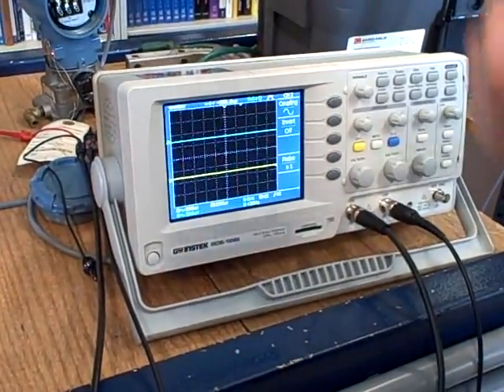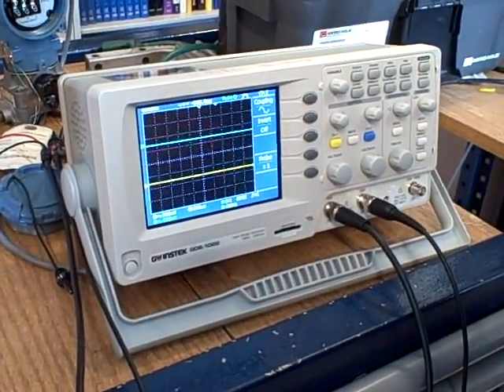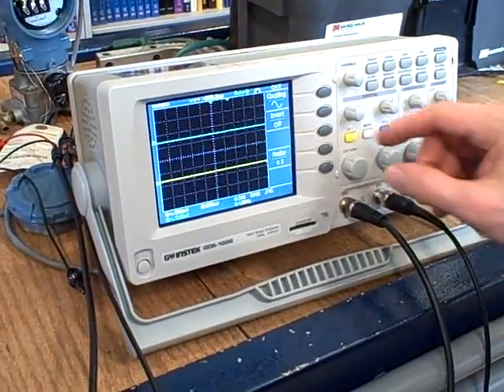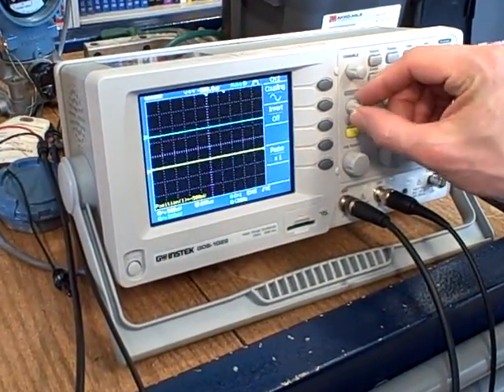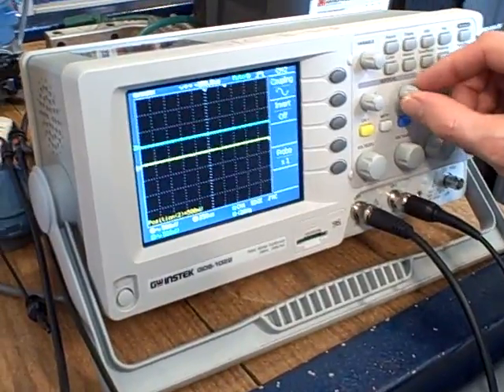We're going to be using a digital capture oscilloscope to take a look at a Foundation Fieldbus waveform. As you can see right here, I've got a dual trace scope set up. Channel 1 is in yellow and channel 2 is in blue.